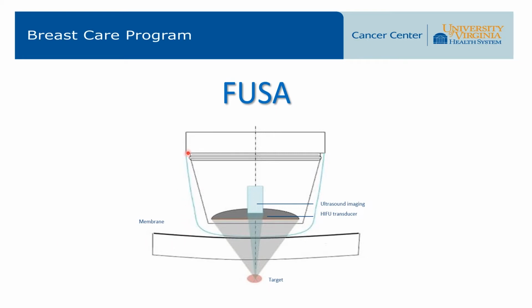And this is the same diagram I showed you earlier, but blown up a little bit. This is from the treatment head of the Theraclion device. In more detail, this is a cooling jacket or membrane that is in contact with the skin, depicted here. This is the high energy HIFU transducer, and this is the ultrasound imaging probe that's embedded in it. We use that ultrasound imaging probe to drive the device and to find the target or tumor.